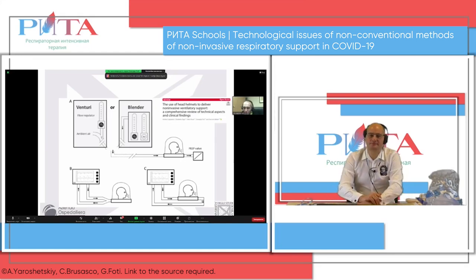The solution is a smooth tube. Not too much flow - if you go over 100, 120 liters, they become noisy. Use earplugs, use the HME filter not as an HME filter but just as a muffler, okay? And put it ideally before the helmet, not after.